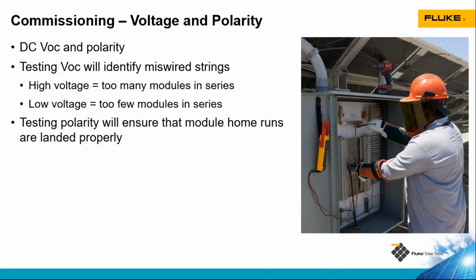Polarity testing is very simple, just making sure that the positives of our strings of modules got connected to the positive and the negative got connected to the negative. And we do this at commissioning because it allows us to easily identify problems that can be corrected through very simple procedures before we put the fuses into the combiner box.